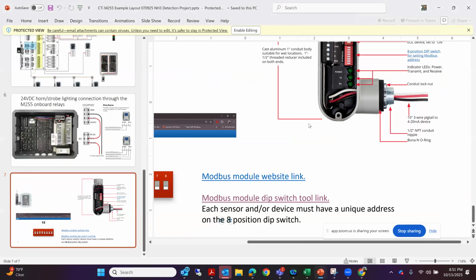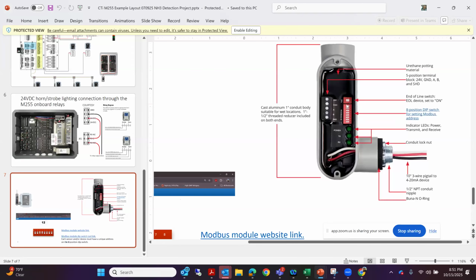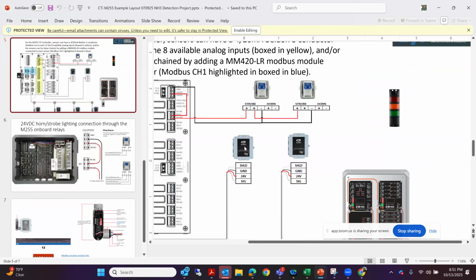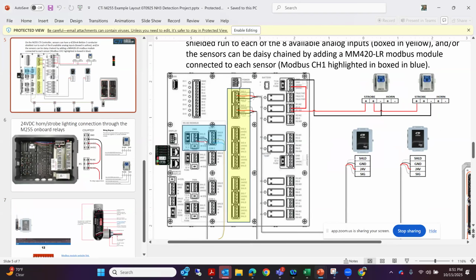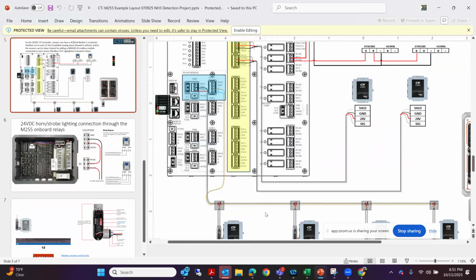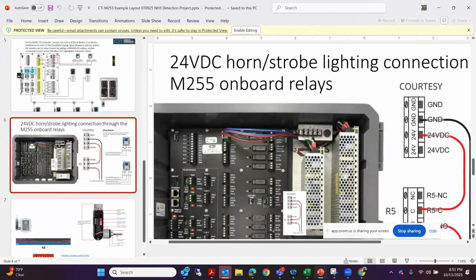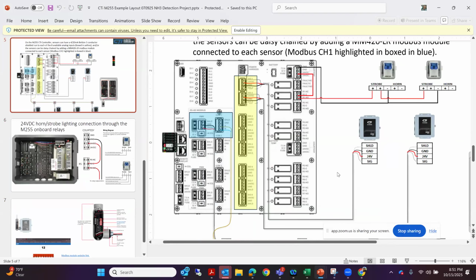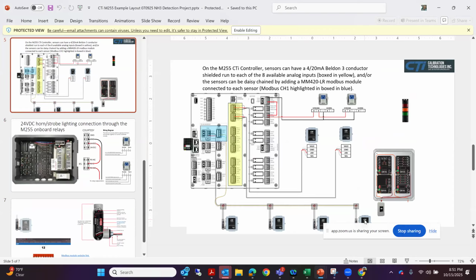If that's sensor 111, I would just match that exactly with this one, open up the door of the enclosure and say, this is Modbus channel 1, and that's going to be sensor 111. So CH1 pound 111 tells me this is on channel 1, and it's sensor 111. On this particular system, we can go out 4,000 feet on this run. We tested it out to 6,000, but you can go out to 4,000 feet.